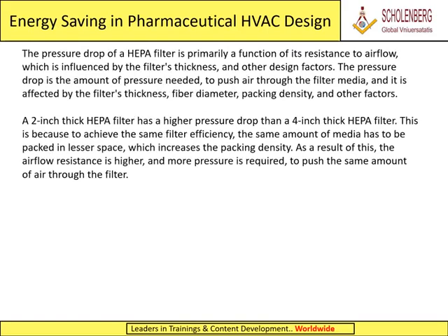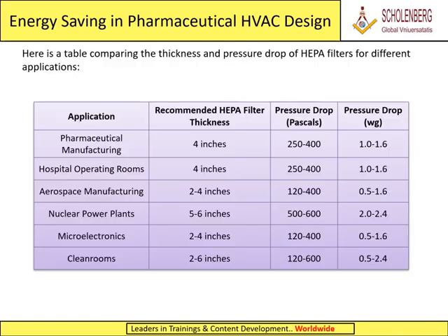The pressure drop of a HEPA filter is primarily a function of its resistance to airflow, which is influenced by the filter's thickness, and other design factors. The pressure drop is the amount of pressure needed to push air through the filter media, and it is affected by the filter's thickness, fiber diameter, packing density, and other factors. A 2-inch thick HEPA filter has a higher pressure drop than a 4-inch thick HEPA filter. This is because to achieve the same filter efficiency, the same amount of media has to be packed in lesser space, which increases the packing density. As a result of this, the airflow resistance is higher, and more pressure is required to push the same amount of air through the filter. Here is a table comparing the thickness and pressure drop of HEPA filters for different applications.